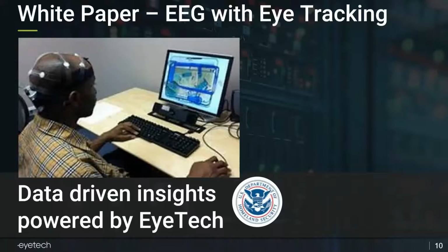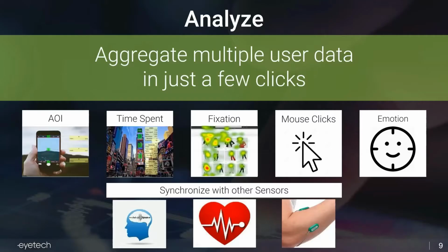Just to give you an idea of tips and tricks, when you're positioning an eye tracking sensor, our VT3 Mini, or the Ion tablet, it is important to position the user about an arm's length away. The head box size is, on the Ion, twice as large as our current VT3 Mini, so 40 centimeters to 80 centimeters, you can position them in front of the device, calibrate, and go.